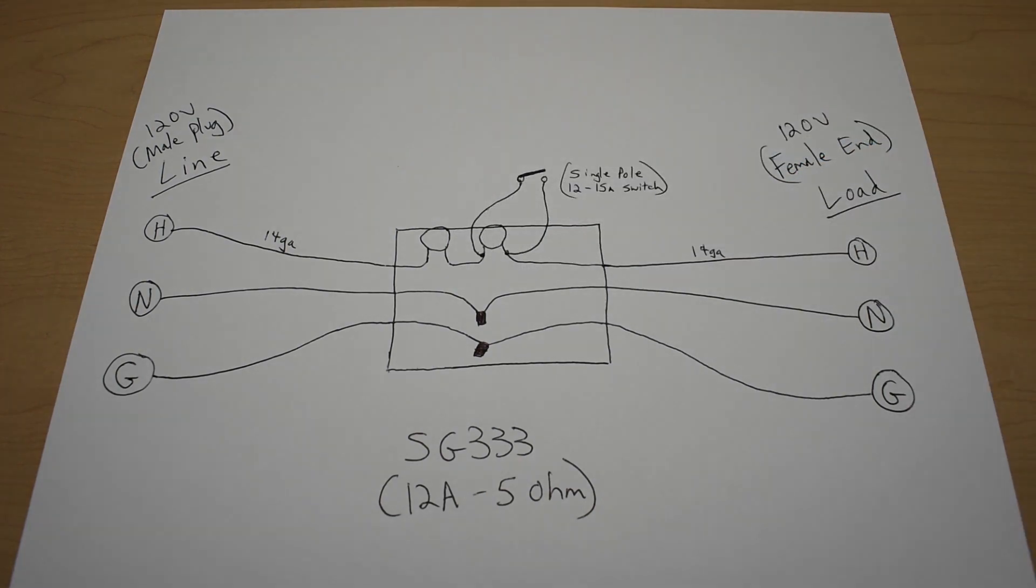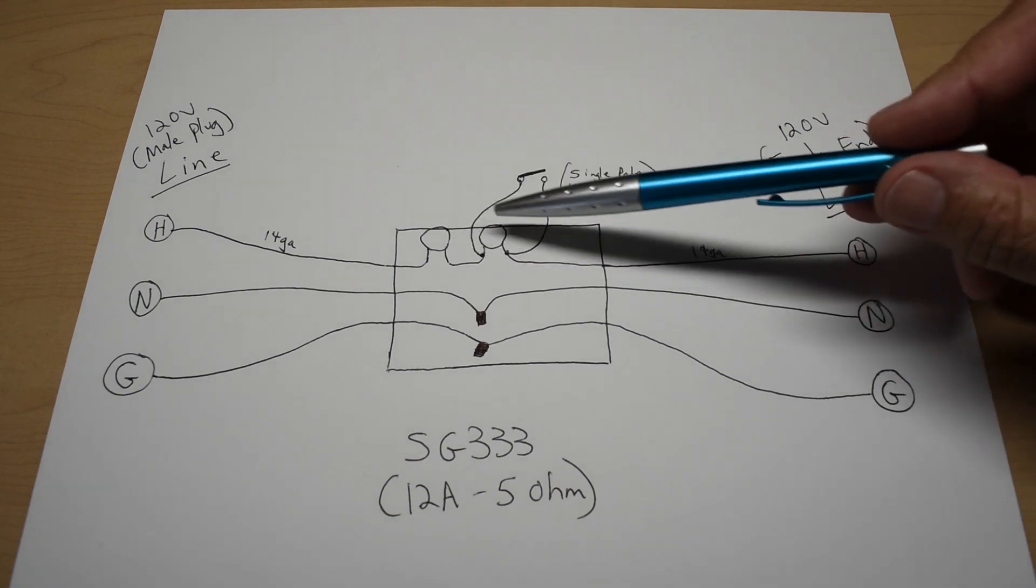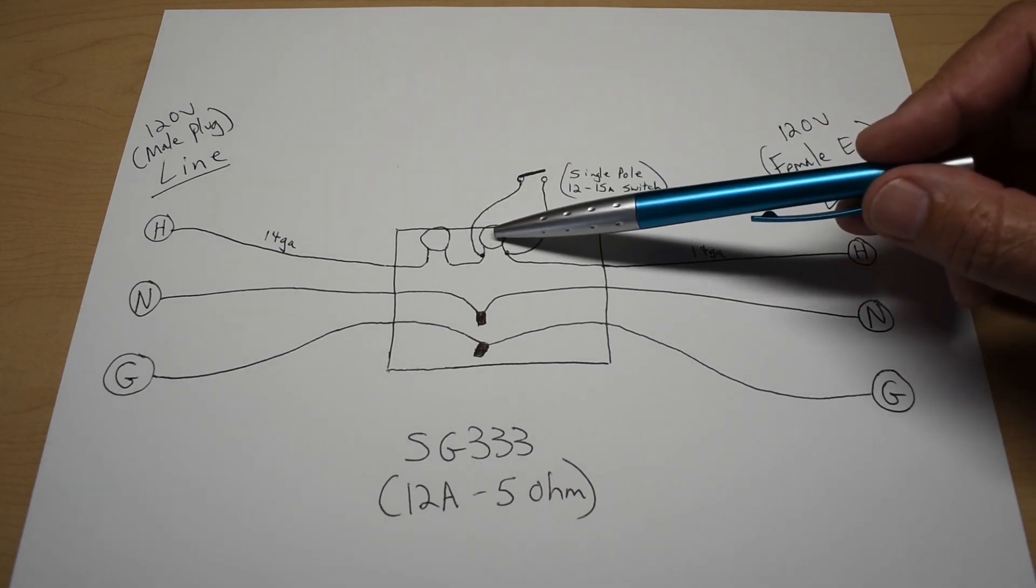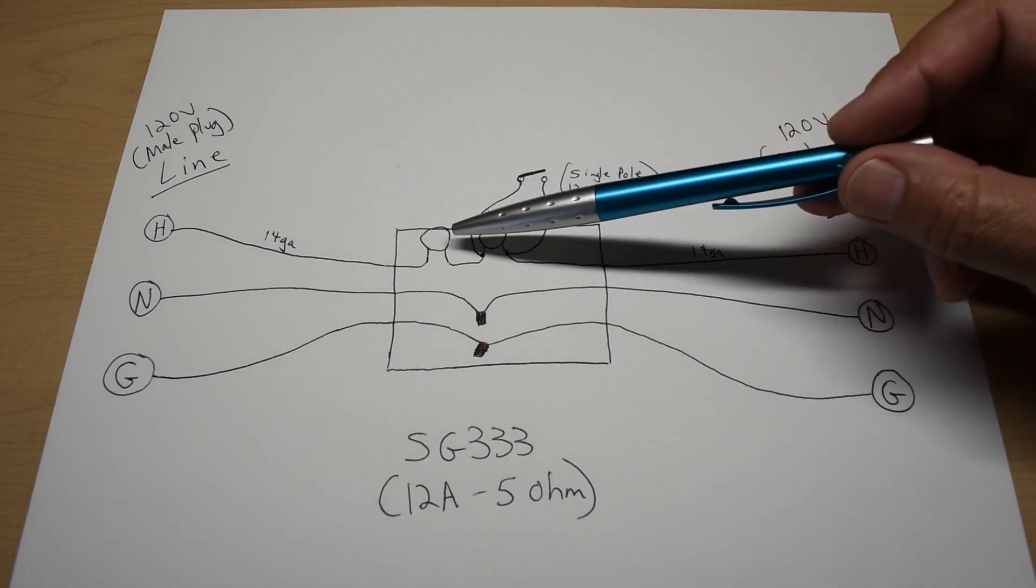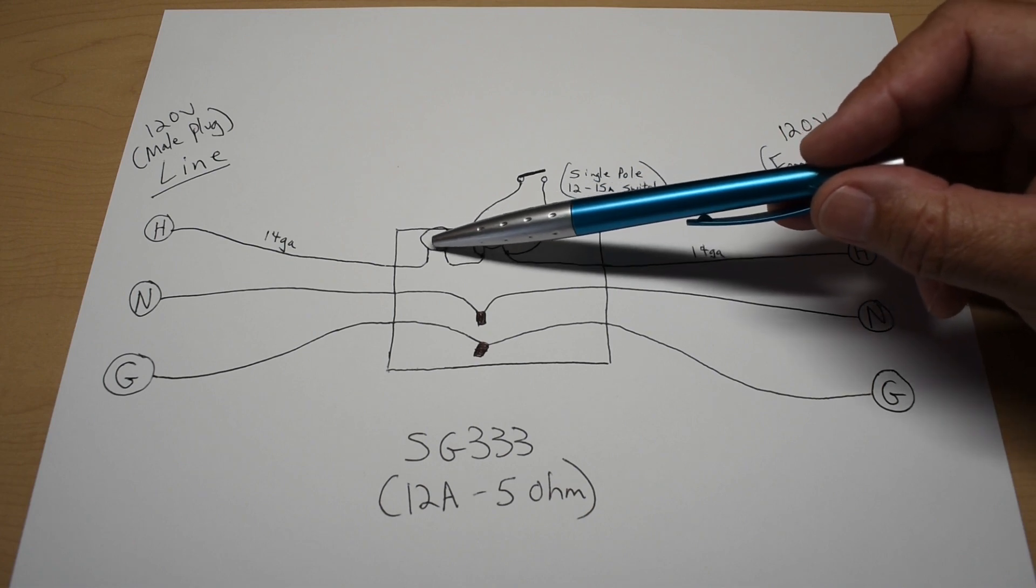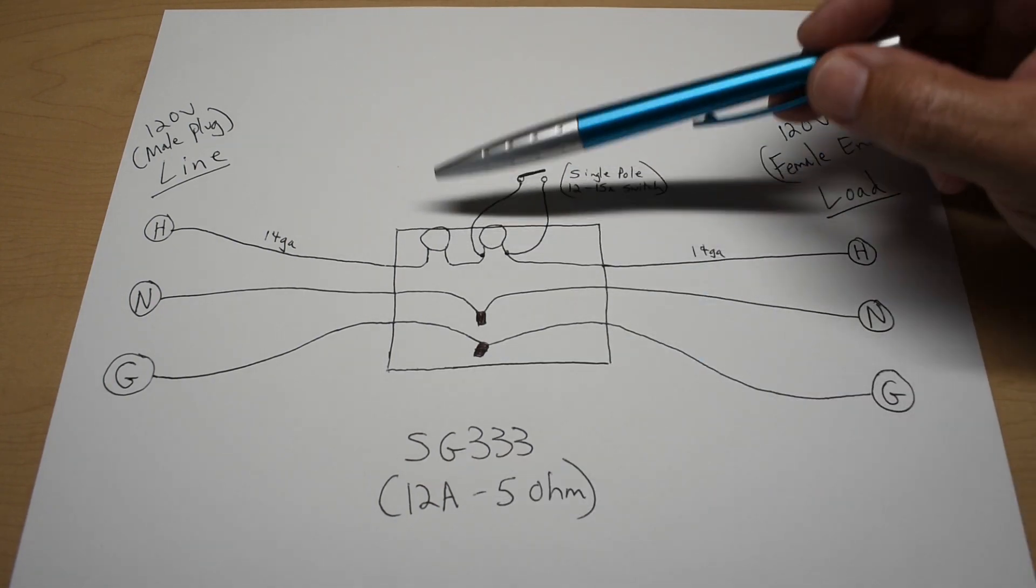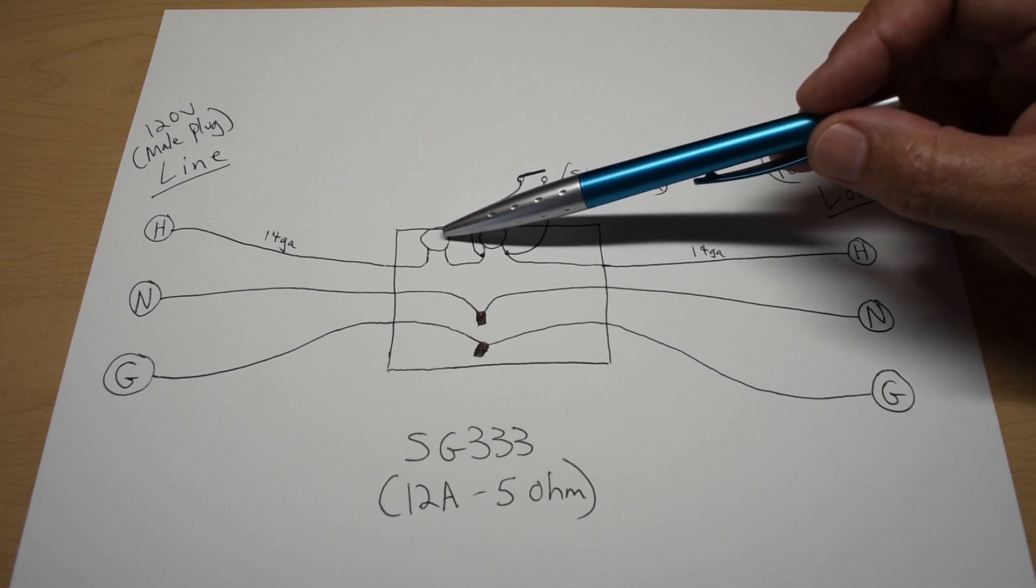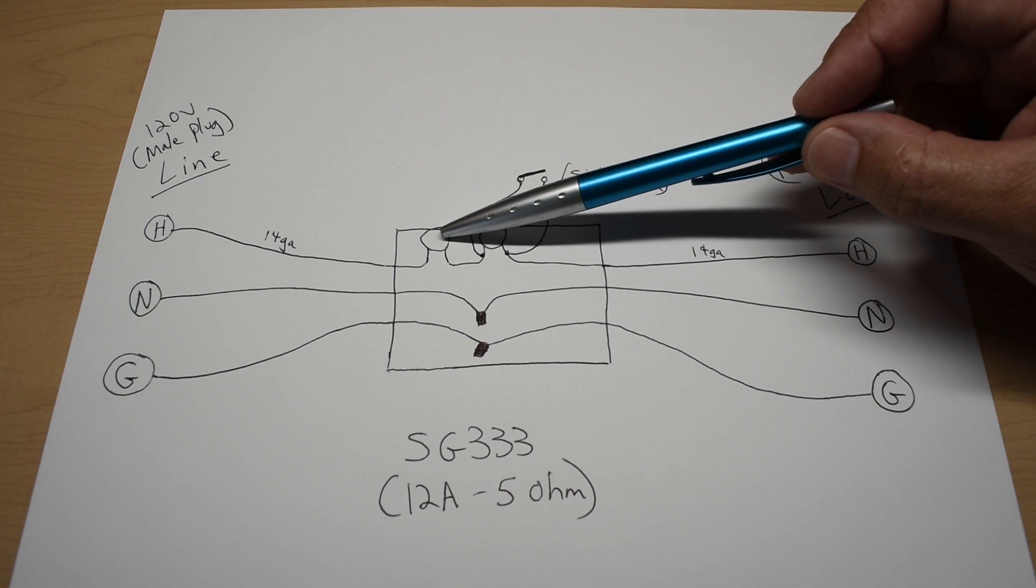Now the NTC inrush current limiters can be used in series like you see here to increase resistance. But you never want to place these in parallel. And the reason for that, they're not exactly the same when they're made. So what's going to happen if you have two in parallel, when the current flows through, one of these is going to heat up first. When it heats up first, the resistance is going to drop to a very low level. And if you were trying to make this a 24 amp by using two in parallel, you're going to end up having the majority of that current go into one of the 12 amp rated inrush limiters.